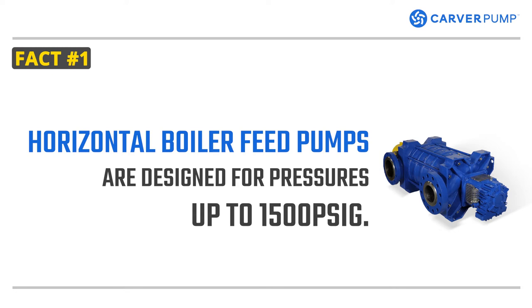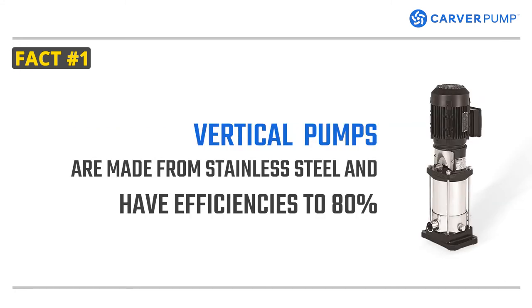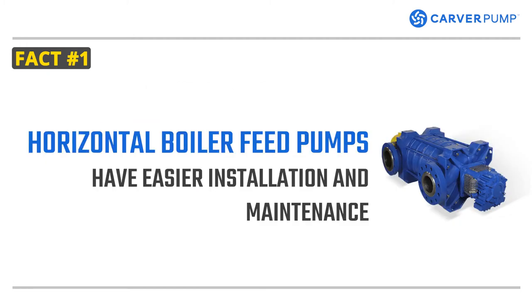Horizontal boiler feed pumps are designed to pump for pressures up to 1500 PSIG. They are often made of cast parts. Vertical pumps are made from stainless steel and have efficiencies up to 80%. Horizontal boiler feed pumps have easier installation and maintenance because changes in ball bearings and mechanical seal can be done with the pump in place through the spacer coupling. Operators can save time from realigning the pump.